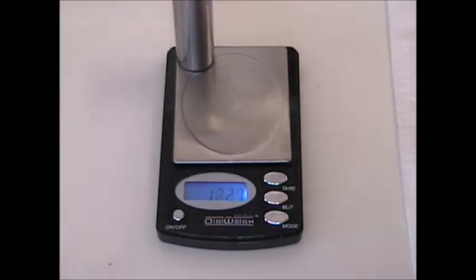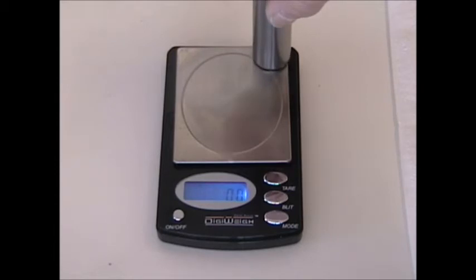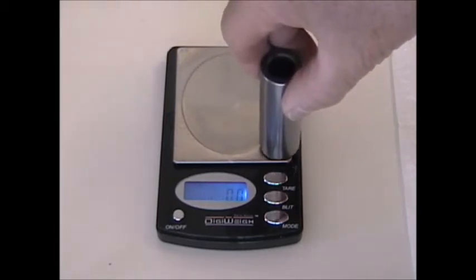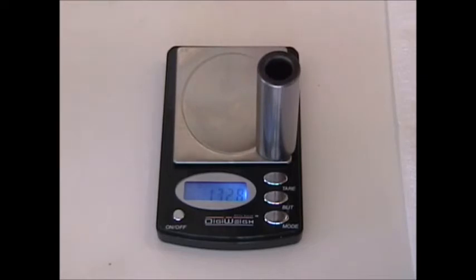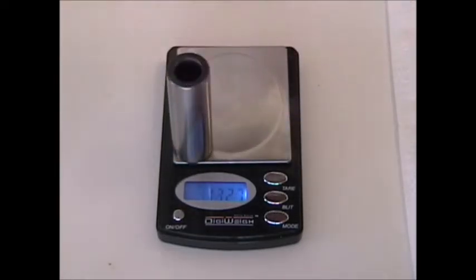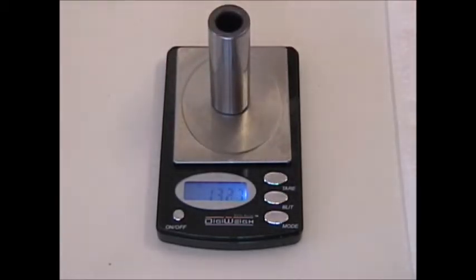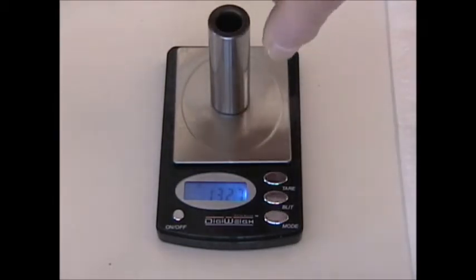Let's see if it makes any difference whether it's in the middle or the outside. 132.7, 132.7, 132.8. So that scale is pretty good. It's pretty insensitive to where you place the part.